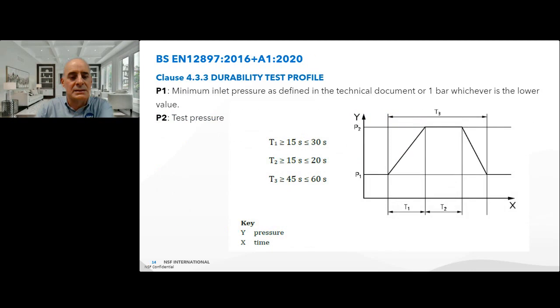You can see here this is the durability test profile. So P1 is the minimum inlet pressure as defined in the technical document, or 1 bar, whichever is the lower value. And P2 is the test pressure. Depending then on whether the 20,000 or 100,000 cycle test is selected would depend on the pressure P2. So there's a ramp rise between T1, and it's got to reach the test pressure within 15 to 30 seconds. The pressure hold time then, T2, is for a time period of between 15 and 20 seconds. But the overall time then for the full cycle, ramp up, hold time, and ramp down has got to be between 45 and 60 seconds.